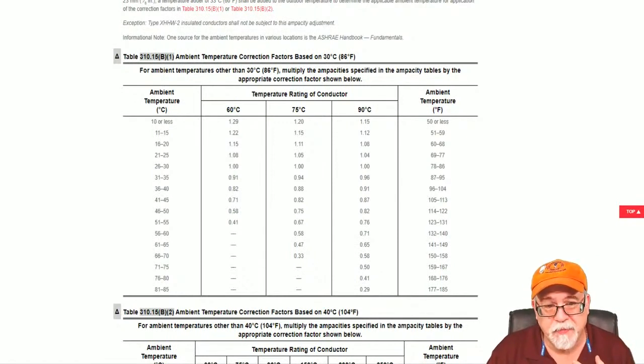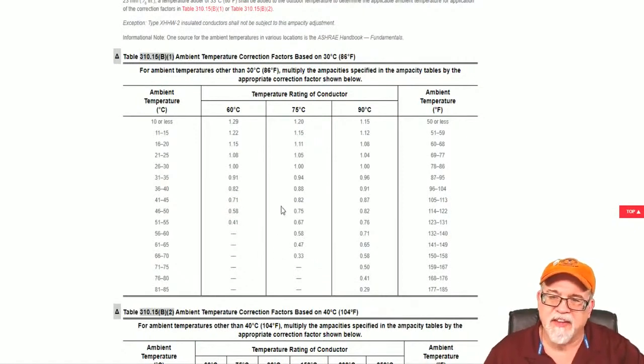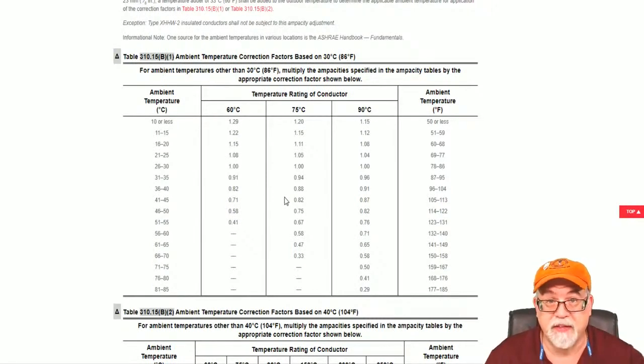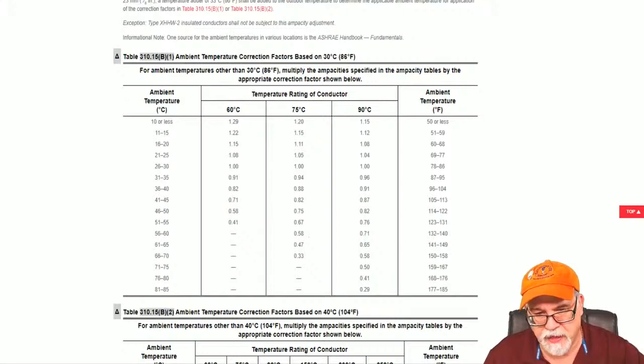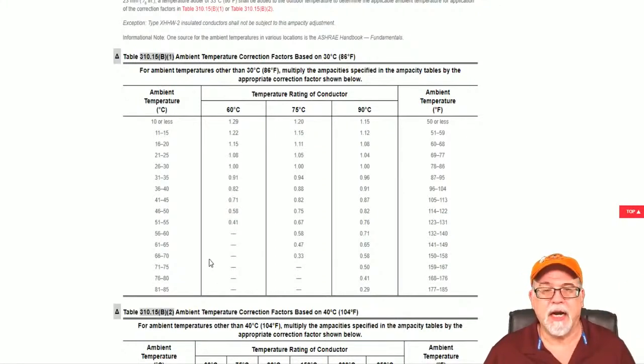But NM cable typically should be 60-degree rated insulation. In order to be 90-degree insulation, it has to be NMB. So we're going to assume that it's 90 for this question, and they just didn't put the dash B on there. So it's 90-degree rated insulation, and it's 130 degrees Fahrenheit in this attic, as if they really know what the temperature is going to be in that attic. We don't know.